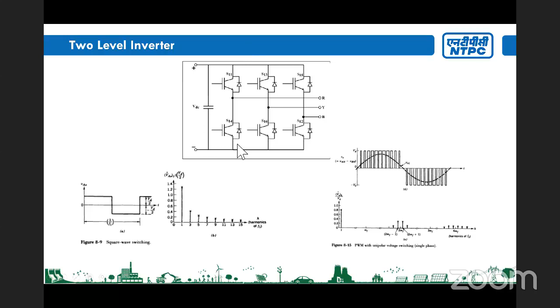Then after 2016 onward, I think we shifted to a 1500 volt topology. In the 1500 volt topology we generally require four devices in series, because one device is 600 volt, so that it can withstand 1500 volt. With four devices in series, the suitable topology is the three-level topology. Two-level means the voltage waveform has 0 and 1, that is why it is two-level. In the three-level topology we have three steps: 0, 1 and 2.